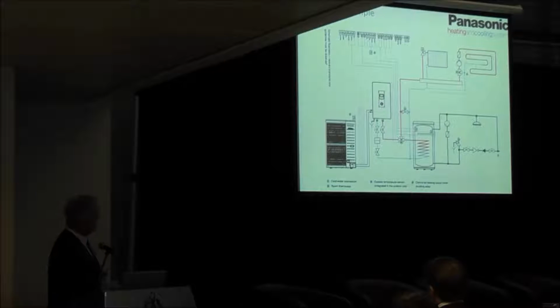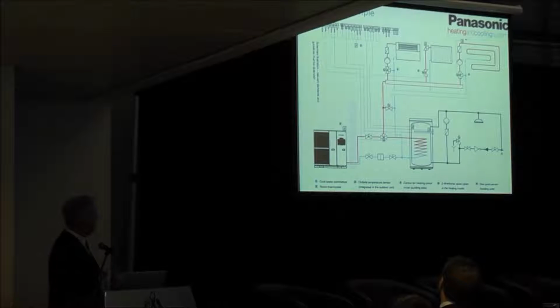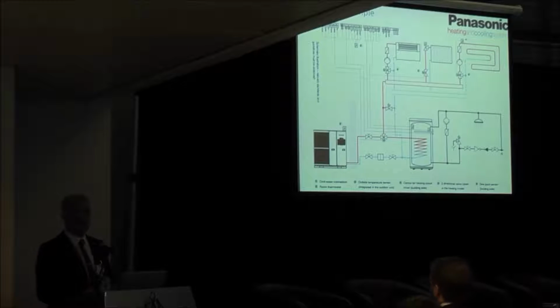On a split system, this is a monoblock system which is more popular. The monoblock is positioned outside the house. You've got flow and return water pipes going into the property. As Vincent explained earlier, because you have water leaving the property, you have to worry about your frost protection. Frost protection is built into the system, but it's electric. So it does protect itself from frost, but it is electric. If you lose power, you have no frost protection. So in a situation like that, it's advisable to introduce glycol or some kind of antifreeze to the system.